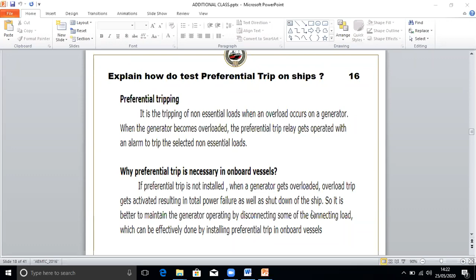Because if the preferential trip is not installed, when the generator gets overloaded, the overload trip gets activated, resulting in total power failure. So it is better to maintain the generator operating by disconnecting some of the non-essential loads. You can see here, the preferential trip gets activated and operates at a time delay, which will disconnect non-essential services in a specific order.